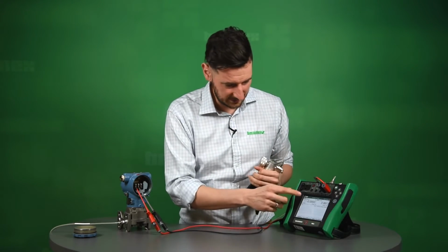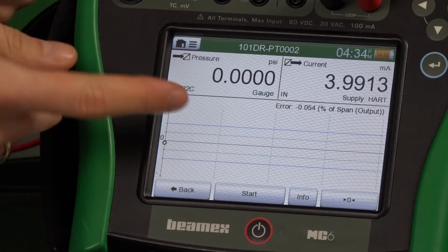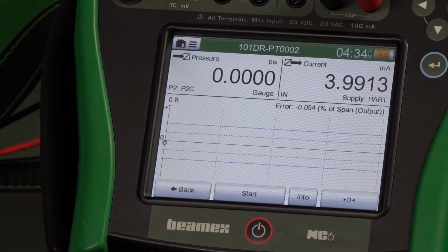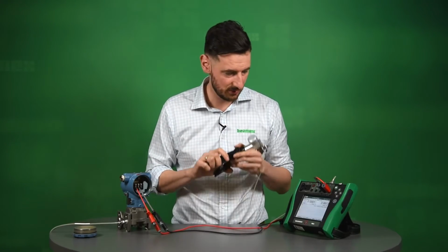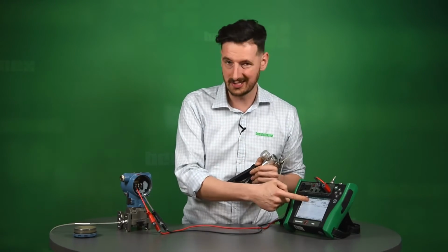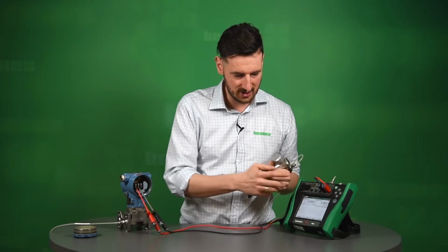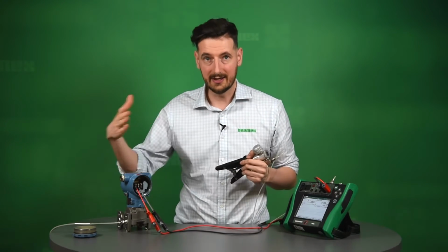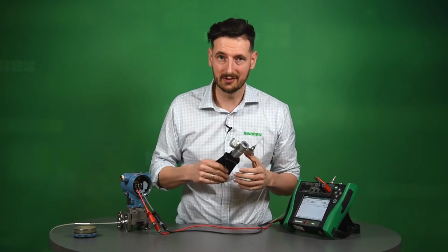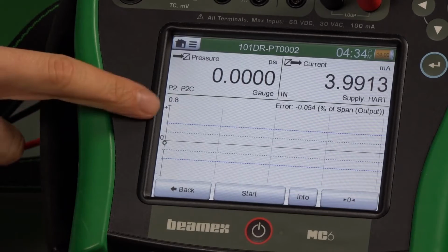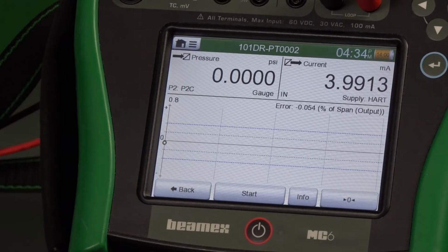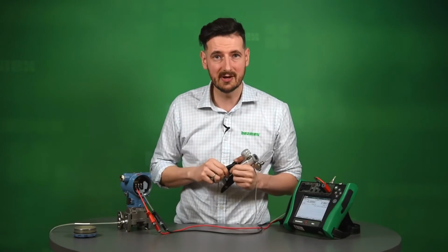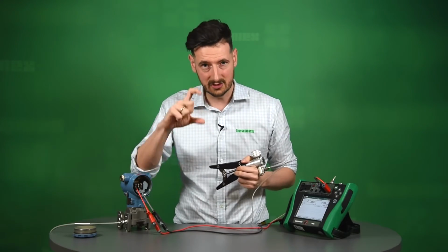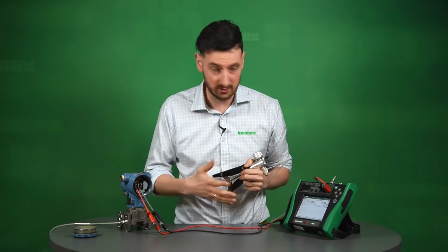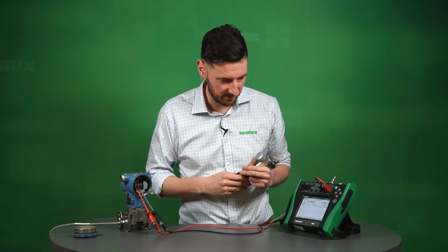But before we do that, let me just quickly explain what we see on the screen. This is a direct feedback from our pressure. So if we're going to start pressurizing the system, you're going to see this changing. And also you're going to see the 4 to 20 changing as well, depending on how much pressure we're going to apply. Also, you can see the lines. These are the tolerance lines, and those conditions that we mentioned before. So if it's above that, it's going to say, please adjust, and it's going to give us information about that.